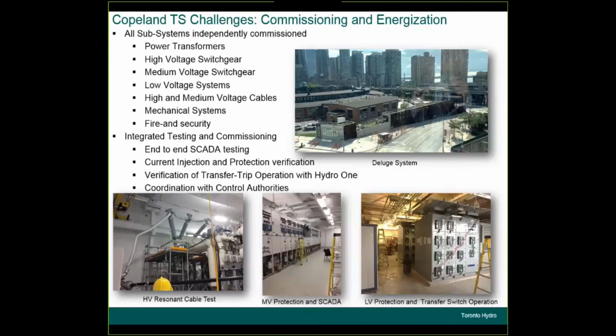One of the aspects of this that was a challenge was coordination with control authorities. We had moved ahead with basic impunity while we were running through the construction process, but once we had energization, the control authority took control of the Hydro One side as well as the Toronto Hydro side of the switchgear in the middle of our commissioning activity, so we had to ensure that we adhered to our work protection requirements moving forward, and that added an additional layer of complication with respect to the commissioning and the energization.